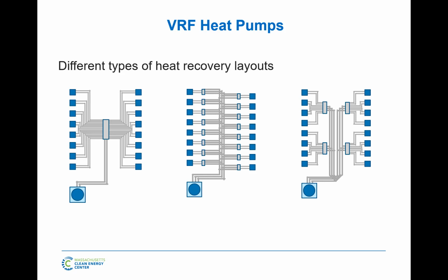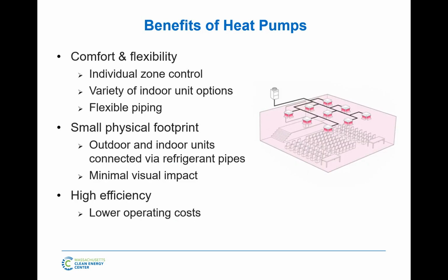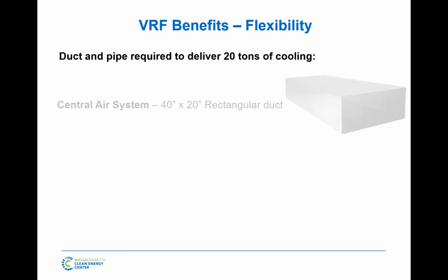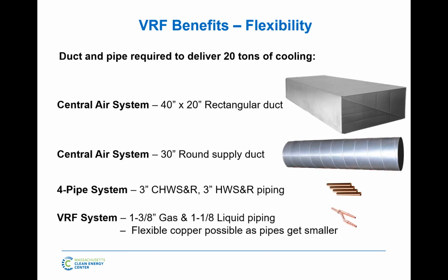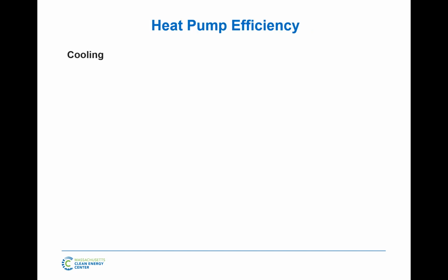Why? Because each of those is feeding a fan coil. Maybe that's as big as 4 tons or so. You can carry 4 tons in a 3/8, 5/8 pipe, which is soft copper. So you run usually hard copper from the condenser down to the branch boxes, branch control devices or changeover devices, then you can run soft copper. I'm going to fast forward here. So this size of pipe is only the main pipes. They get much smaller when you get inside the building.